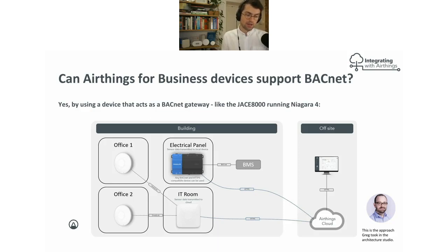A very common one would be, for example, having a BAS controller like a Tridium Jace 8000 that we saw Greg was using in his installation. That would make this data available as data points for actuators around the building. Currently, the only way to do this is through the RESTful API, like the Active Framework or the oneSite solution drivers for Niagara, but also now with MQTT, you can use the native MQTT capabilities built into Niagara 4 and onwards.